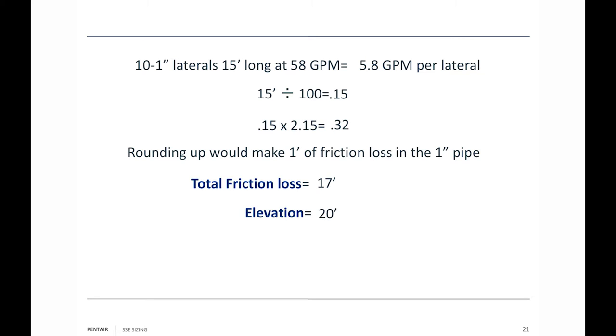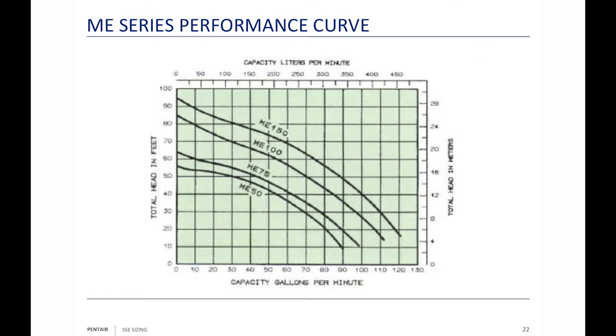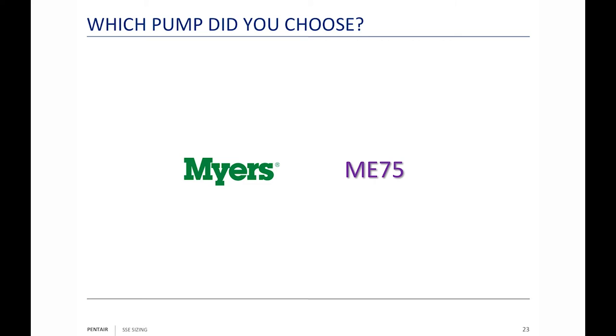Our elevation difference is 20 feet, the required squirt is 4 feet, and total friction loss is 17 feet (16 in two-inch + 1 in one-inch pipe). Adding those together: 58 gallons per minute at 41 feet of head — that's what we're looking for in a pump. Looking at the ME series performance curves, 58 GPM at 41 feet of head falls right on the ME75 line, so we choose the Myers ME75 for this job.